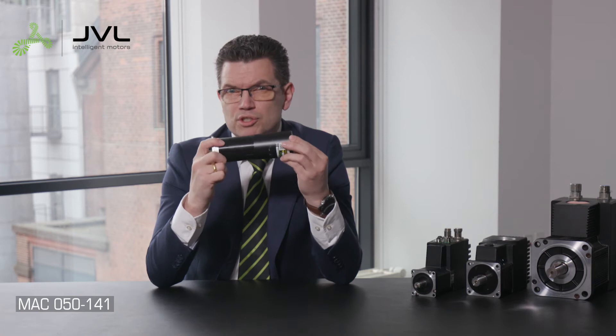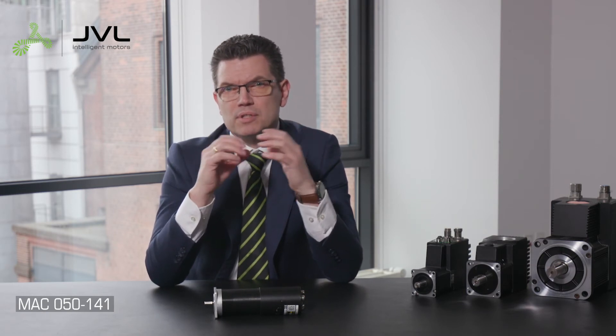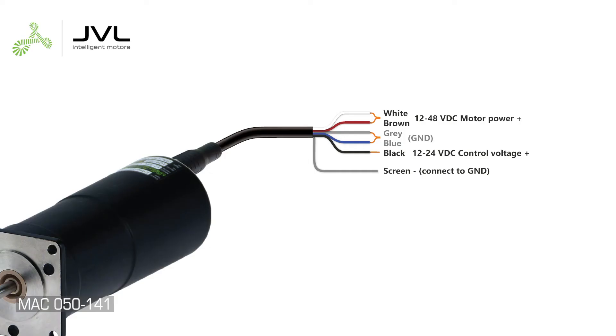The chosen motor voltage decides the maximum speed. It's important to choose a power supply that has three times the nominal power, as it has a peak power of 300%. The M12 5-pin power connector is unified on all JVL motors and M12 power cables.